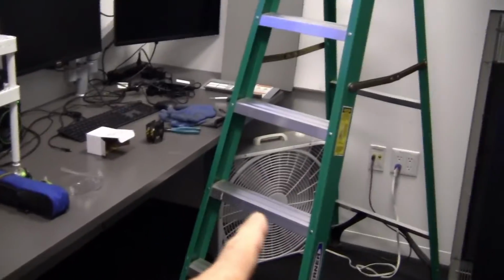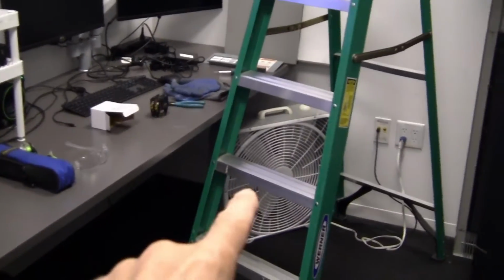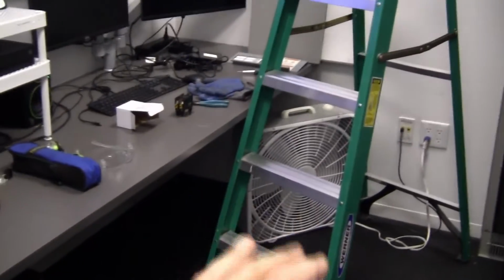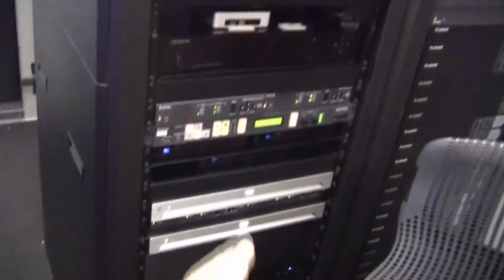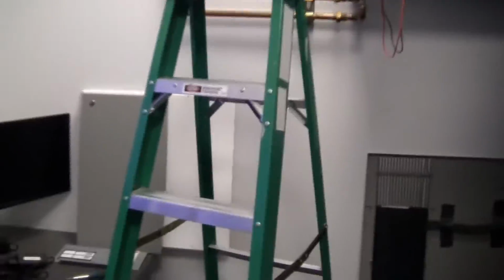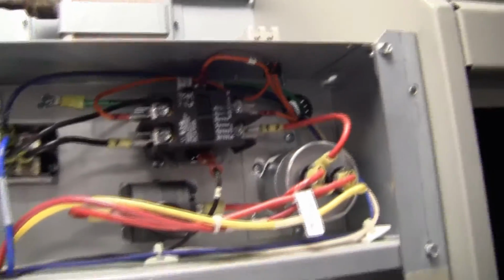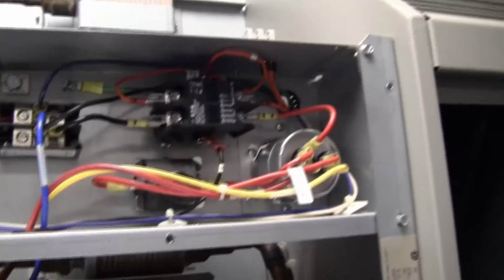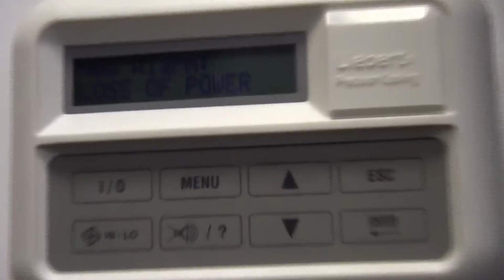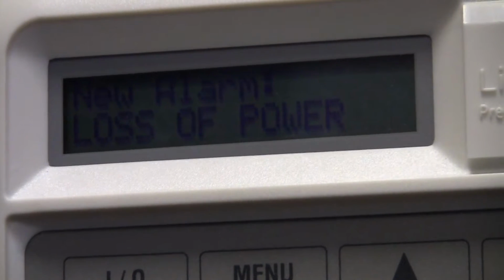Okay, I had put a fan on there while I was gone to the supply house. I shut the fan off now to have as little ambient noise as possible for the video. There's still equipment running here that has fans that make some noise that I can't shut off. Now, I've already put the brand new contactor in, and it was a slam dunk to put it in because everything was all pre-labeled for myself. Let's crawl up here into the ceiling and take that disconnect switch right there and throw that on.